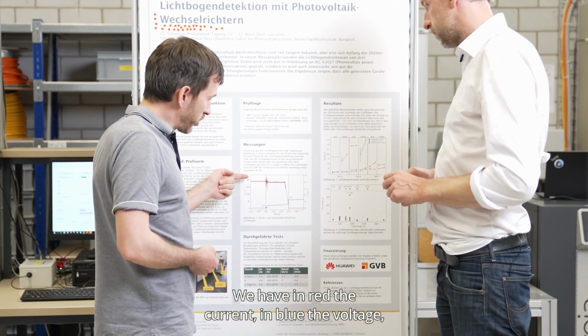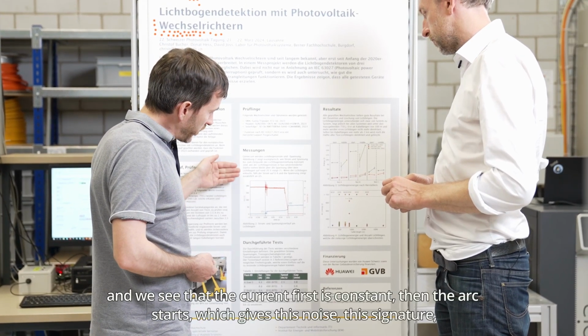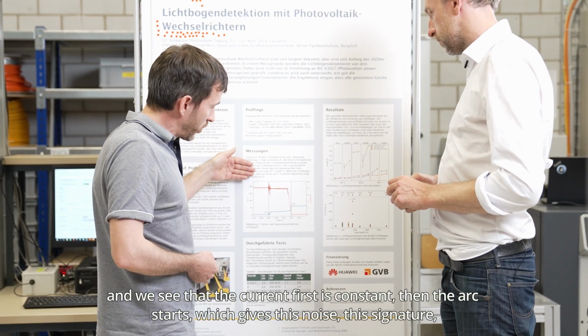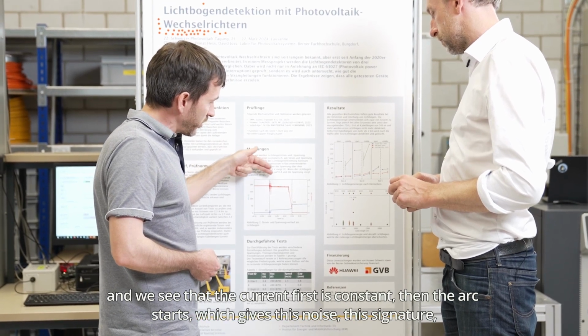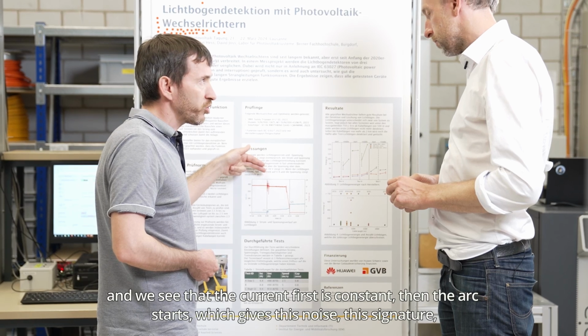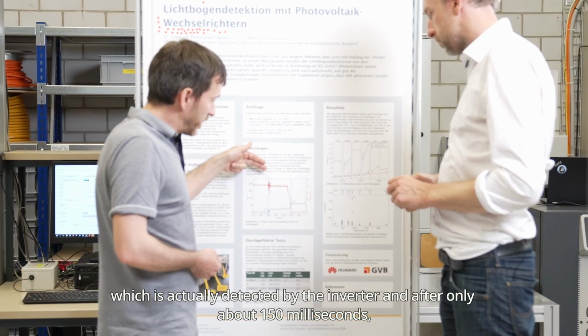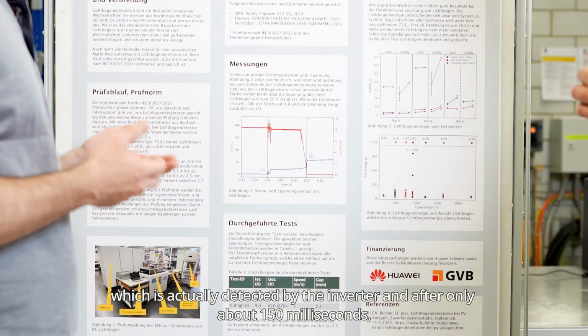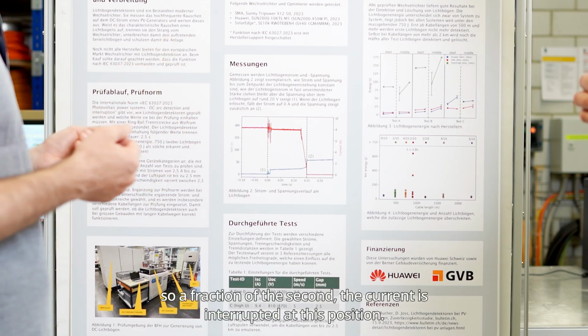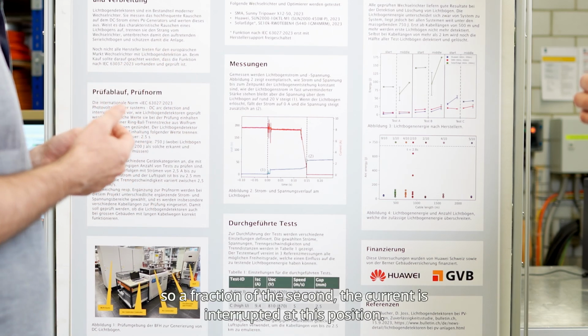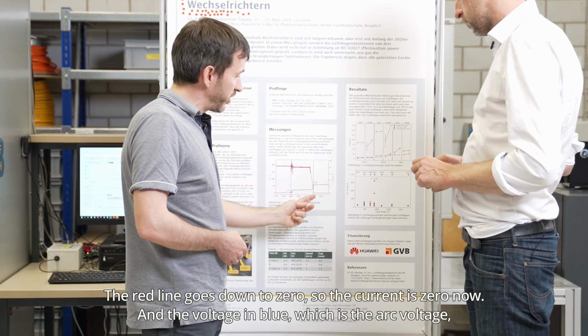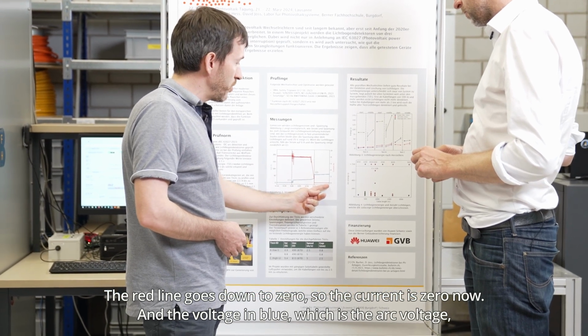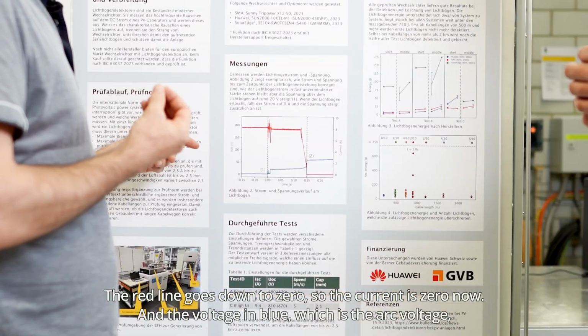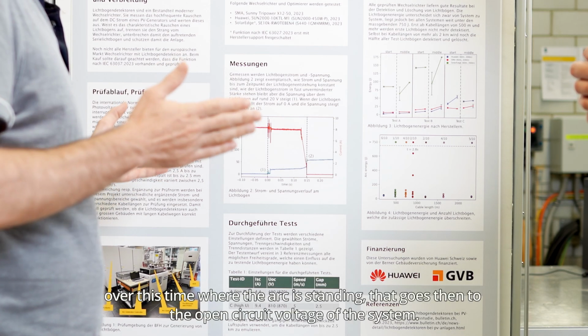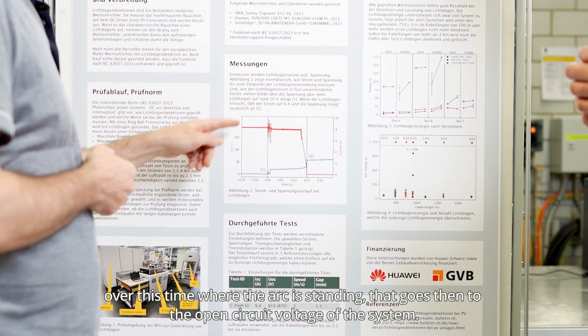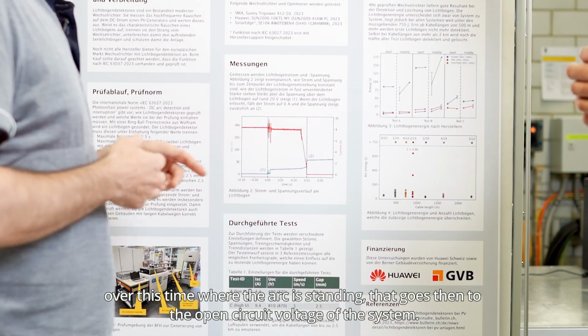We have in red the current, in blue the voltage, and we see that the current first is constant, then the arc starts, which gives this noise, this signature, which is actually detected by the inverter. And after only about 150 milliseconds, so a fraction of a second, the current is interrupted at this position. The red line goes down to 0, so the current is 0 now. And the voltage in blue, which is the arc voltage over this time where the arc is standing, then goes to the open circuit voltage of the system.